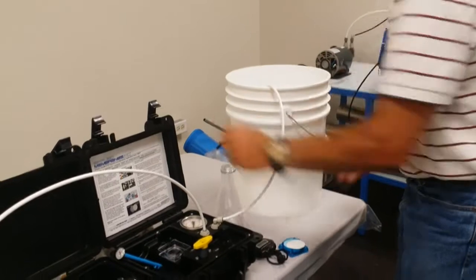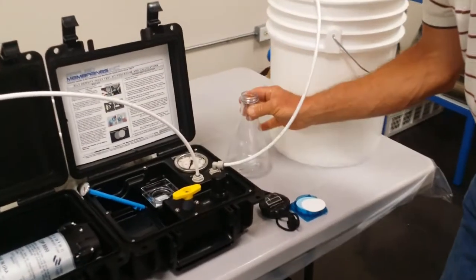We'll time it, 15 minute total test. We'll run 500 mils once at the first and then 500 mils again at the last and then we'll come back, do our math and that gets our SDI.